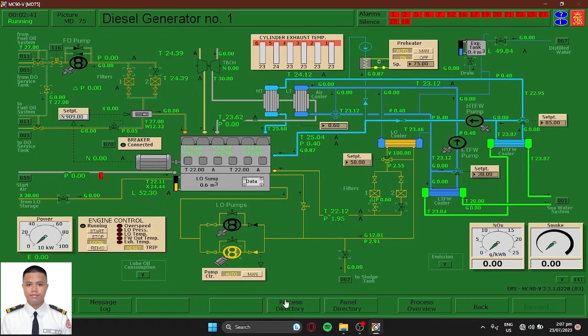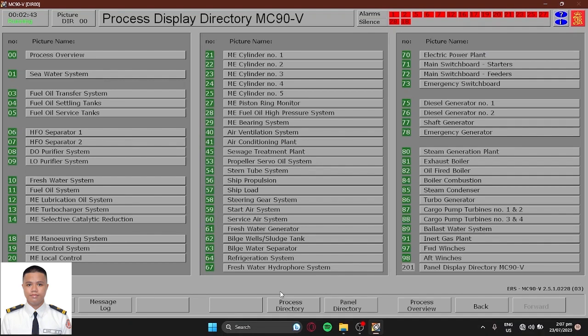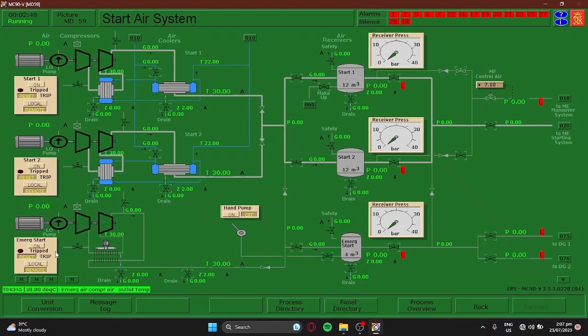So next step is to go back to process directory. Go here, number 59, start air system. Focus in this area, the emergency compressor. So what you're going to do here is first to drain the valves to remove any water accumulated in the compressors. So once this goes to 0, close the valves.